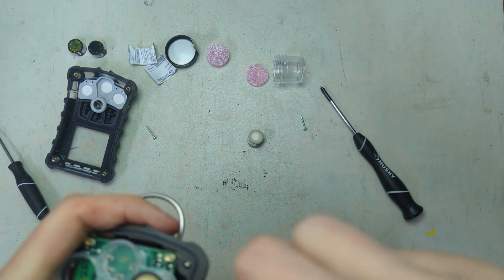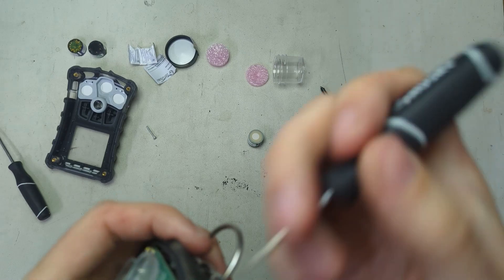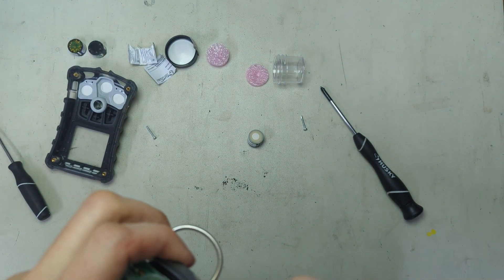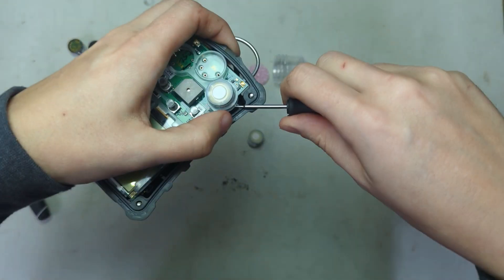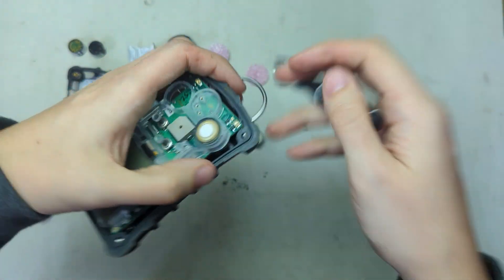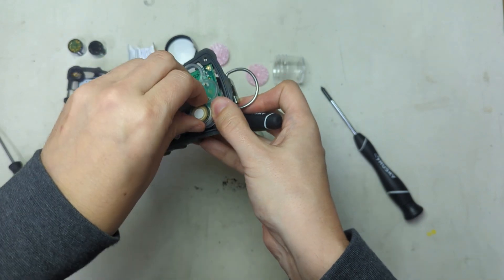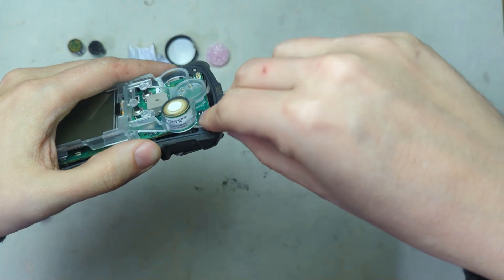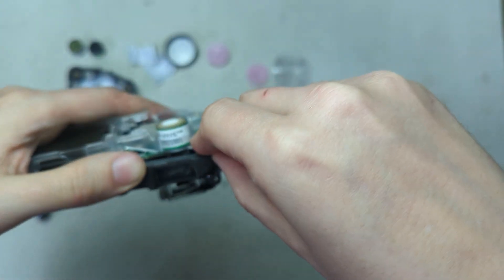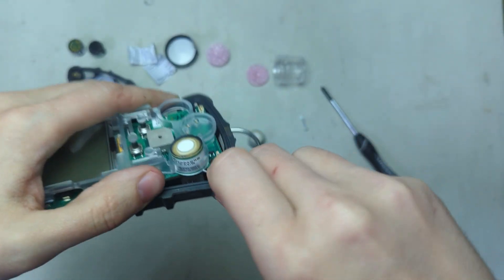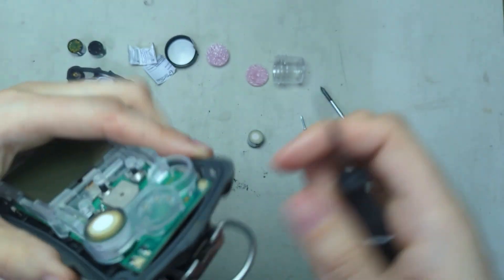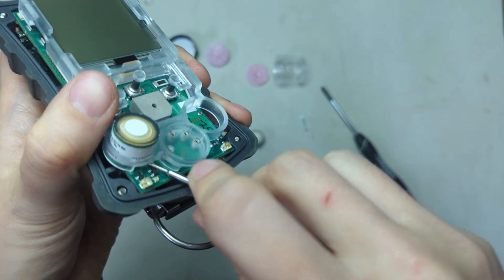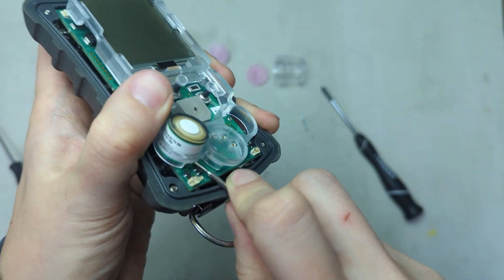This is pretty obviously a sensor that has leaked and has gotten some electrolytic fluid on the board. And one thing you'll find with these units, is when that goes on these cells, it can really ruin the board and it might never function again. So if this happens and you can't get it off, you want to check if you're under warranty, number one, and if you are, you want to send it in to a repair center that can help take care of this for you.